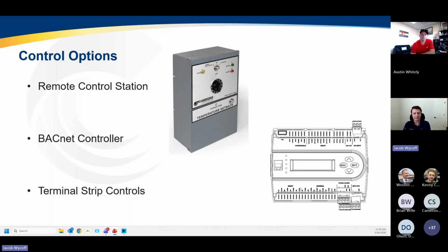The second option would be a BACnet PLC controller. For those spaces that have a building automation system or a building management system, it would have some pre-programmed makeup air unit sequences in there to allow it to interface and be controlled and monitored by the building automation system. Finally, we could remove that BACnet controller and simply provide terminal strip controls to allow for controls or a third-party controller by others. This would allow them to send the burner and blower enable signal, as well as modulate the burner up and down. They would also get some feedback in the form of digital outputs from our unit to be able to monitor the status of the unit.